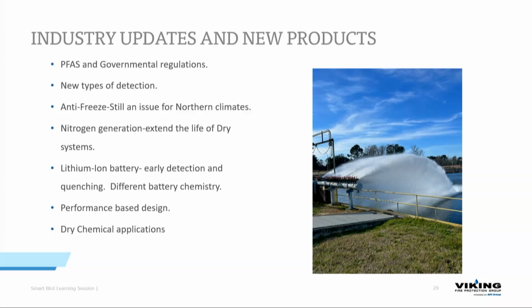Nitrogen generation, extending the life of dry systems. I don't think that we quote a dry system anymore without a nitrogen generation component as an add alternate. And I was really skeptical when this came out that it was just another gimmick. And I've seen the results, and I have to say that if you're not using nitrogen generation inside your pipes, you're not getting the full life cycle out of that dry system. What we're doing is we're taking oxygen out of the inside of the pipes and replacing it with nitrogen. Oxygen is super corrosive to steel, and over time in that wet, moist environment, it'll break down a dry system very quickly.